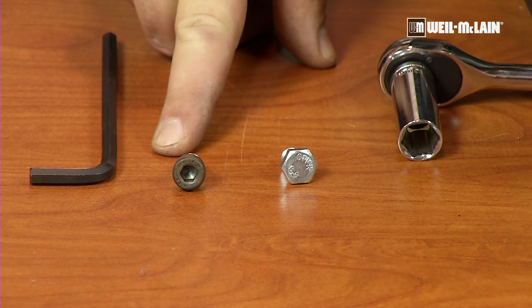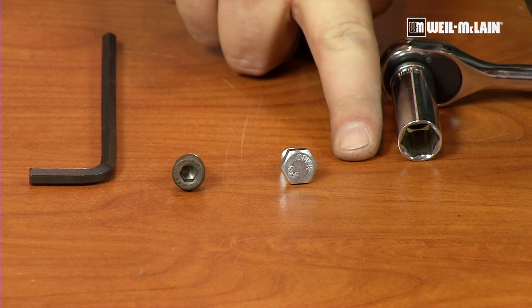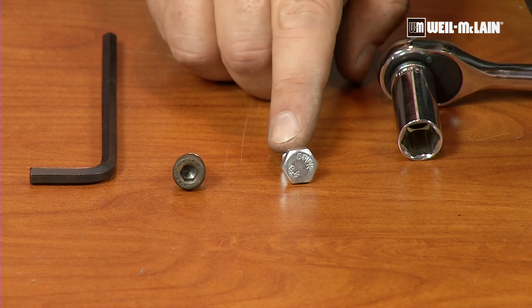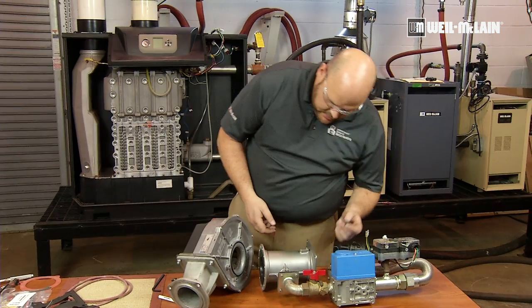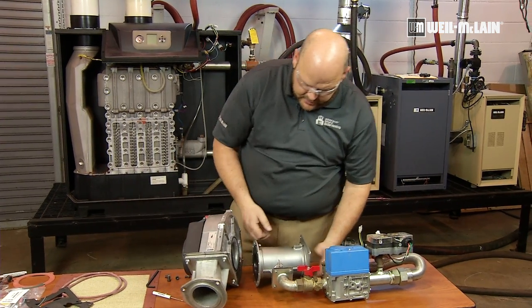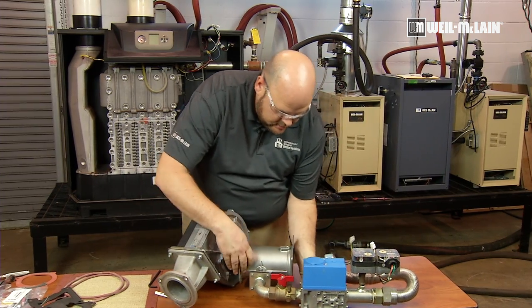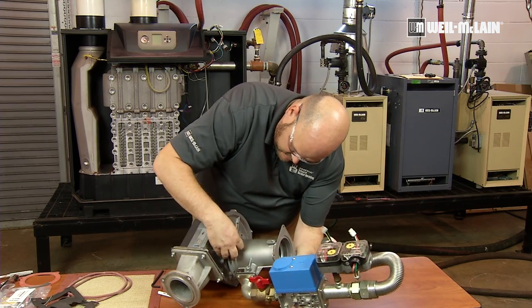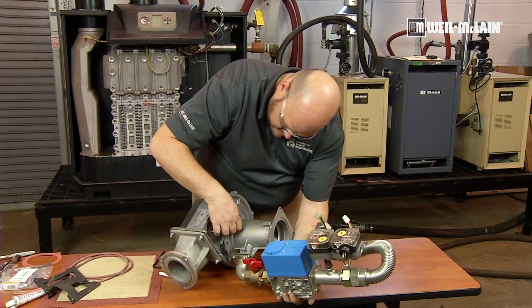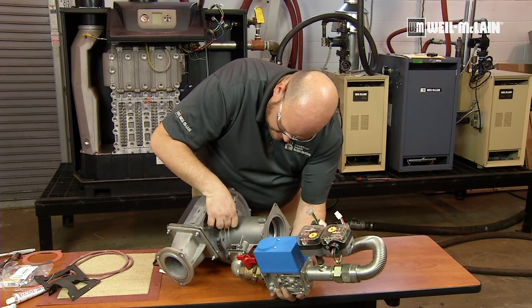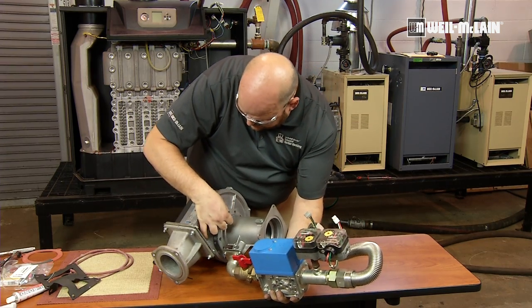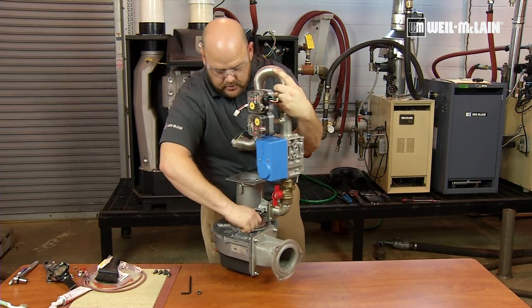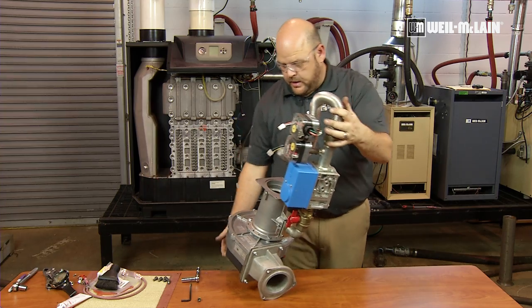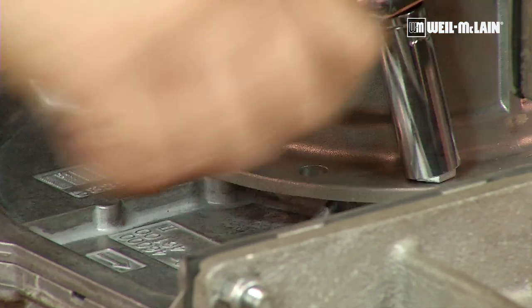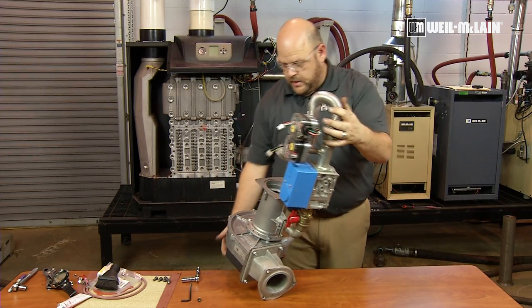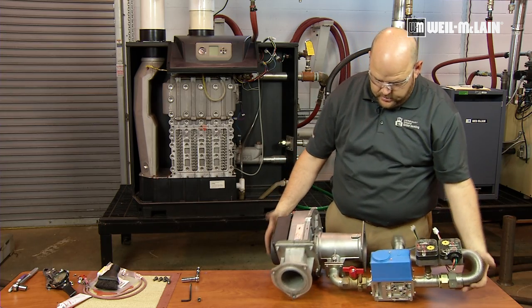Previous models may have used the 6mm Allen, and we have now included the 13mm hex bolts in the kits to replace them. Now we can put our burner, put our gas valve back on. Support the gas valve with one hand and start your screws with the other. Being careful not to damage the blower. We can set in the upright position and we'll work around the venturi. That puts our blower, gas valve, and air pressure switches back in position.